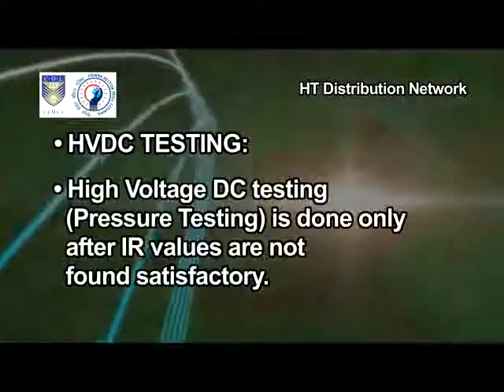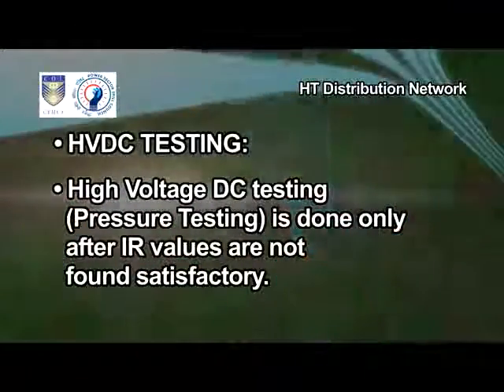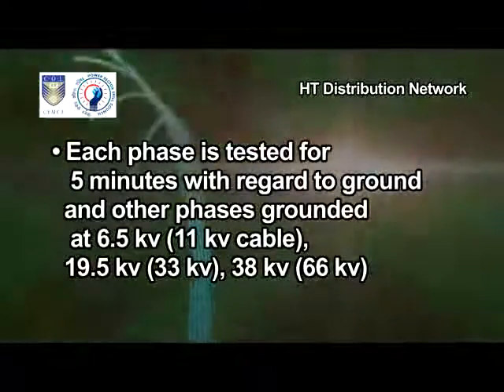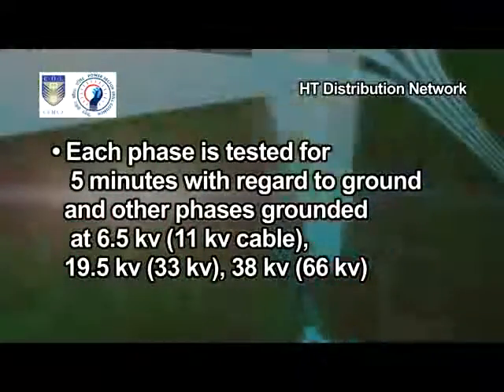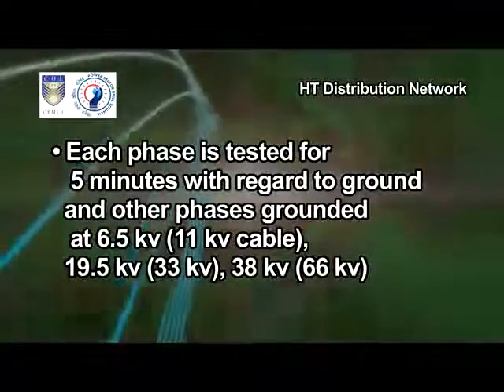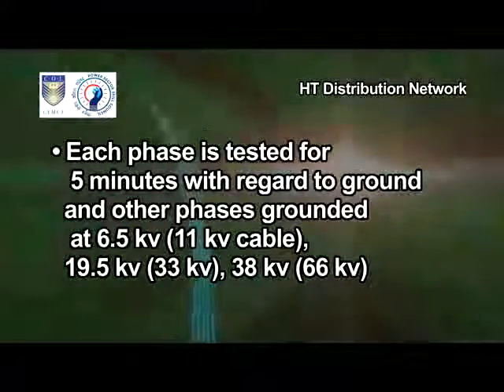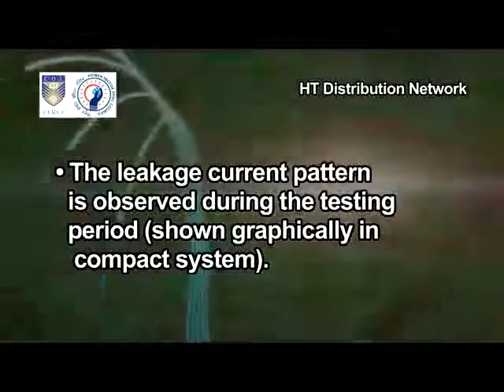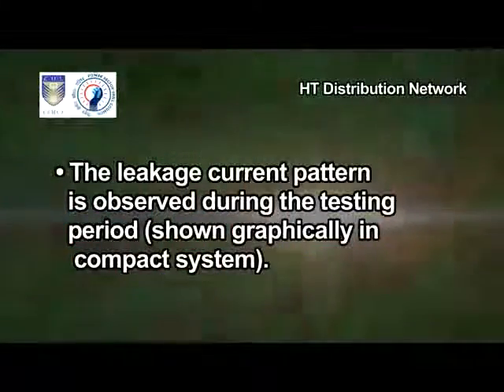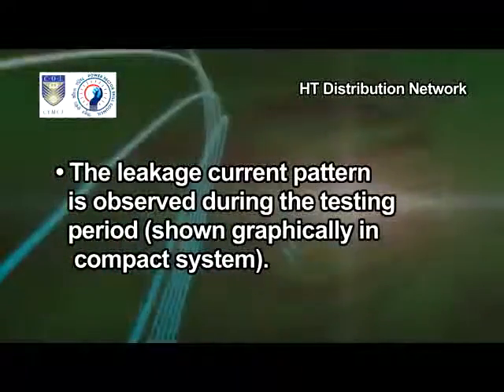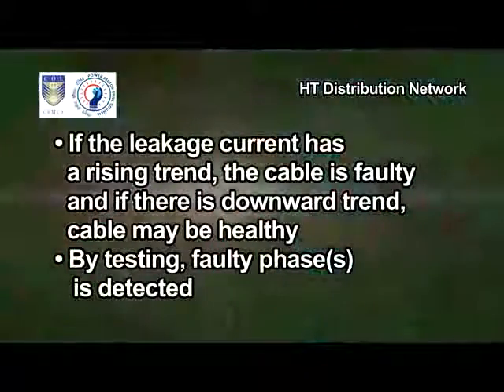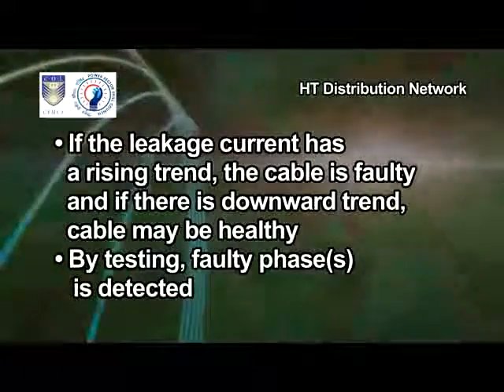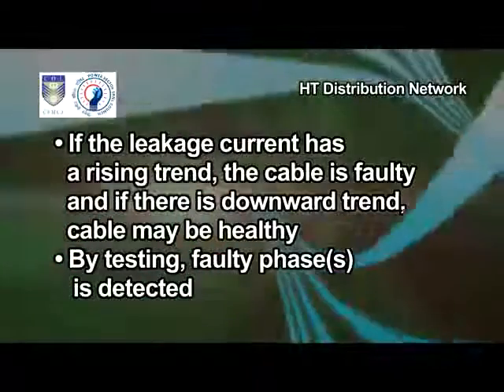HVDC testing — high voltage DC pressure testing — is done only after IR values are not found satisfactory. Each phase is tested for 5 minutes with respect to ground, with other phases grounded, at 6.5 kV for 11 kV cable, 19.5 kV for 33 kV, and 38 kV for 66 kV. The leakage current pattern is observed during the testing period and shown graphically in the compact system. If the leakage current has a rising trend, the cable is faulty; if there is a downward trend, the cable may be healthy. By testing, the faulty phase or phases are detected.